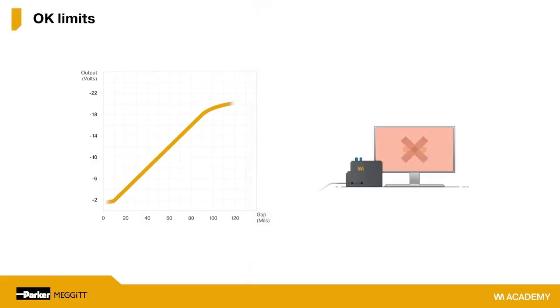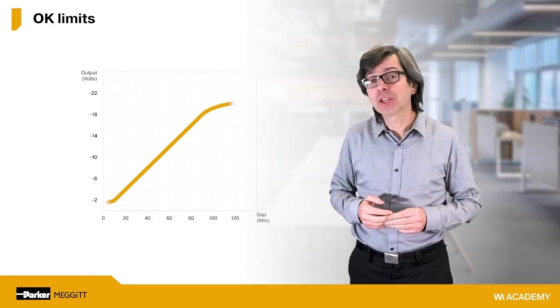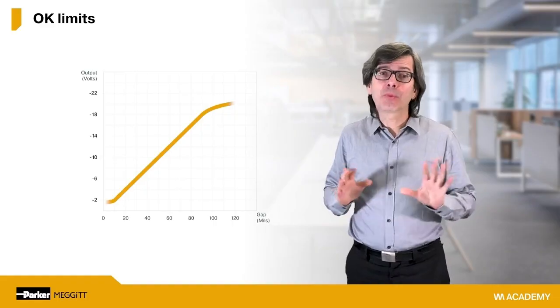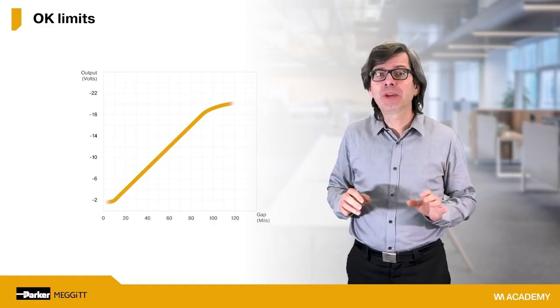It's important also to note that the OK limits are established in the monitor. The transducer itself does not self-detect when it's operating outside of this linear range. It simply provides a voltage output based on the observed gap that it detects.